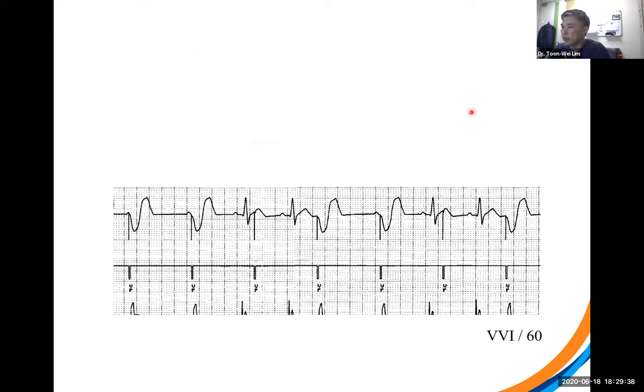So here's an example of undersensing. As we follow along the slide here, you'll see that there are pacing spikes with the QRS, pacing spike with the QRS, so far so good. What happens here though is that there is a P wave followed by a QRS, but straight after that, a pacing spike goes in. This would suggest to you that this pacing spike is clearly inappropriate. In fact, this is quite risky, the fact that it's coming on the T wave. There's another intrinsic QRS followed by another pacing spike, and again, you'll see that the interval from the QRS to the pacing spike is much shorter than the V pace interval, suggesting that this is not an appropriate pacing spike because the device has failed to sense this QRS.